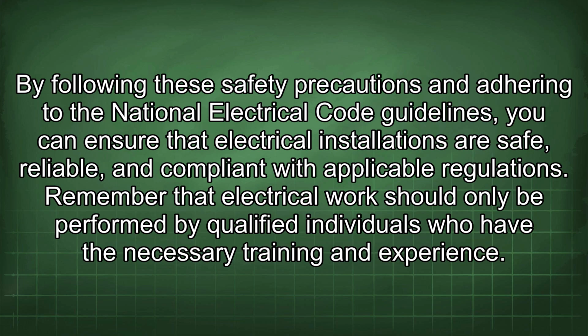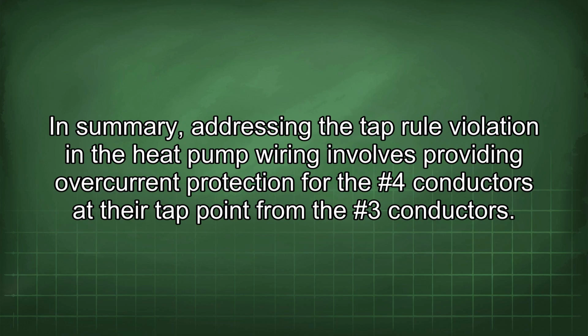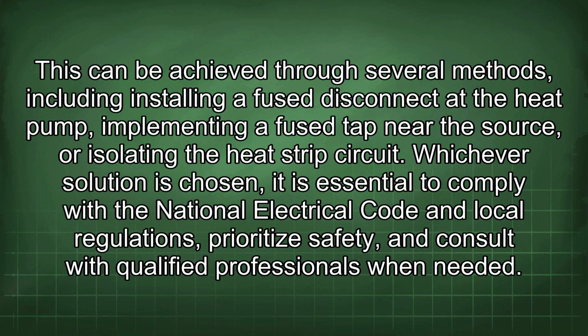Remember that electrical work should only be performed by qualified individuals who have the necessary training and experience. In summary, addressing the tap rule violation in the heat pump wiring involves providing overcurrent protection for the #4 conductors at their tap point from the #3 conductors. This can be achieved through several methods, including installing a fuse disconnect at the heat pump, implementing a fuse tap near the source, or isolating the heat strip circuit. Whichever solution is chosen, it is essential to comply with the National Electrical Code and local regulations, prioritize safety, and consult with qualified professionals when needed.